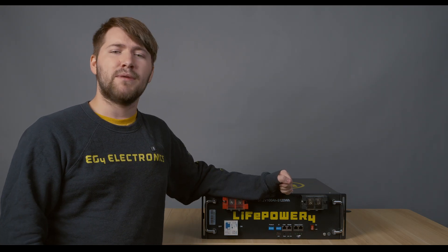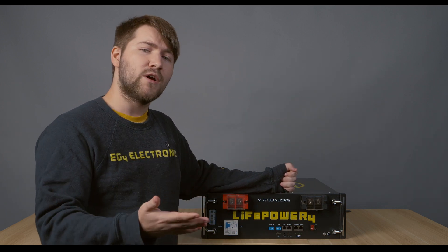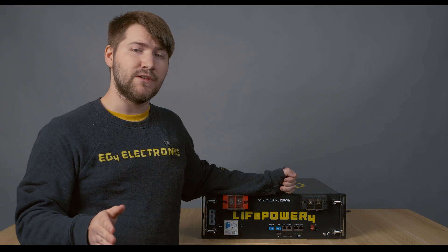Now, what if you're making a battery bank out of only V2s? In that case, you'll want to make sure that each battery has a unique ID. The one consideration that's different from the V1 LifePower4 is that your master battery will have dip switch ID one set to down. That is different from the V1 and is a consideration to make. You set your protocol however you would like.